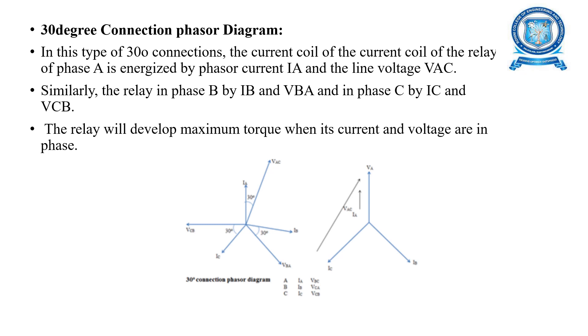In the 30-degree connection phasor diagram, the current coil of the relay for phase A is energized by phase current IA and line voltage VAC. Similarly, the relay for phase B is energized by IB and VBA, and phase C by IC and VCB. The relay will develop maximum torque when its current and voltage are in phase, as shown in the diagram.